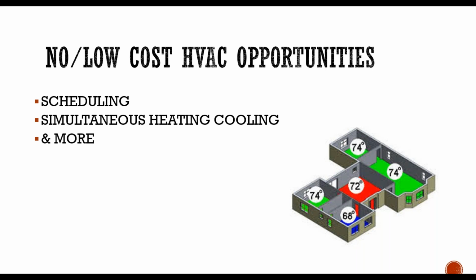So if you can get good control of your HVAC, then that's more than half the battle. So I'm a big believer. Again, I don't sell thermostats, I'm a neutral third party here, but I'm a big believer in it because it equips you to make better decisions. Let me say one last thing on adjusting the temperature set point. One degree change can save 1.5% on the HVAC portion of your bill. So going from an average of 70-degree cooling to 72-degree cooling can have a 3% impact on the HVAC portion of your bill. So again, be as aggressive as you can on that.